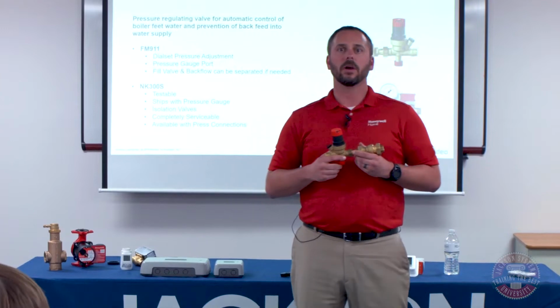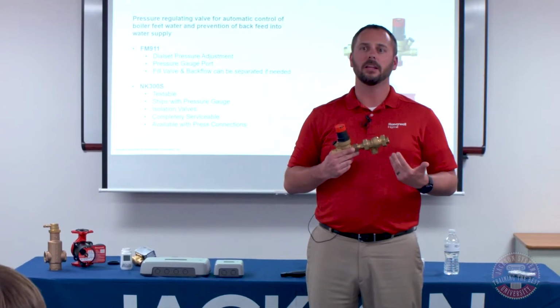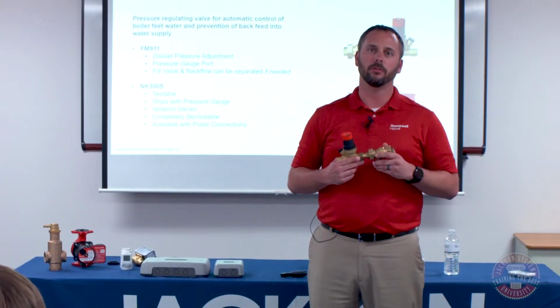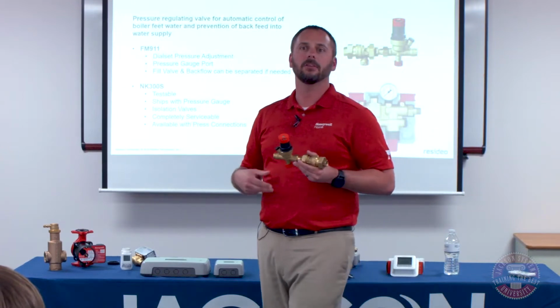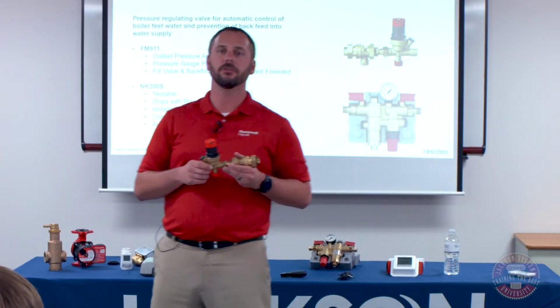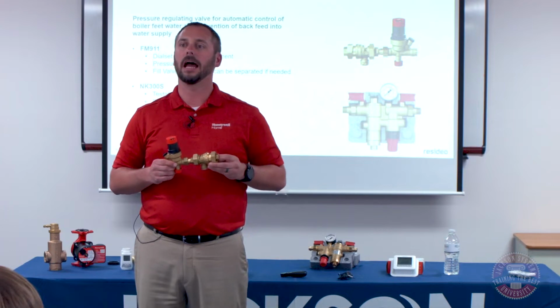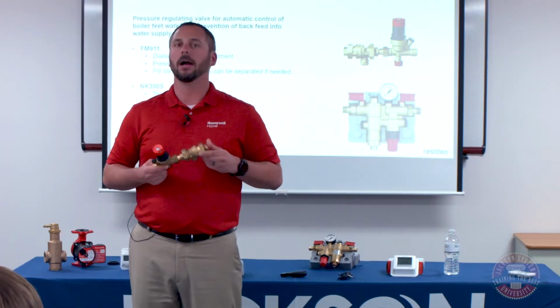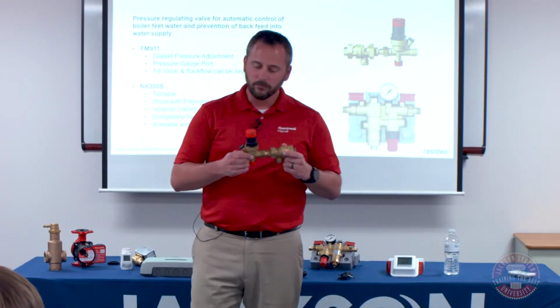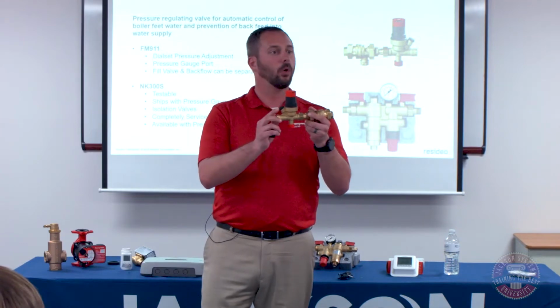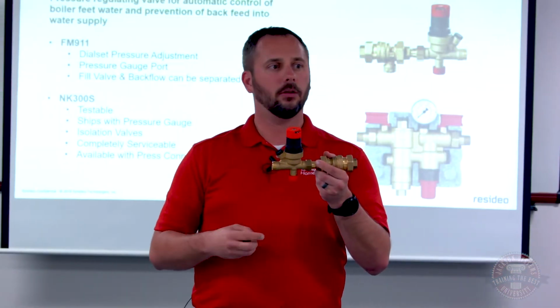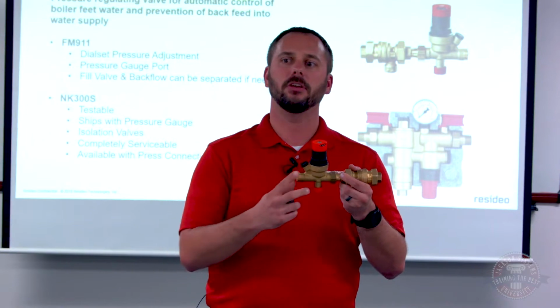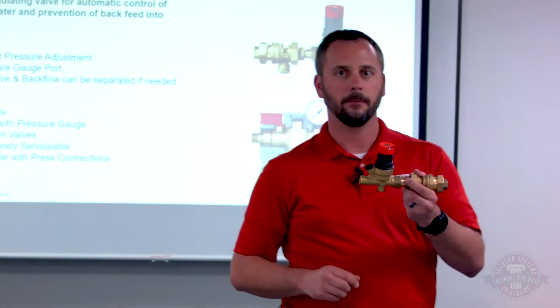We've raised that because we've seen more and more condensing, modulating and condensing boilers coming out. And what's happened with that is typically they need slightly higher pressures than we used to see with the old 12-pound guys that we used on cast iron and copper fin boilers. We also ship it with a gauge port, so you can take this plug out, add a pressure gauge, and you can see your pressure at the point of source.